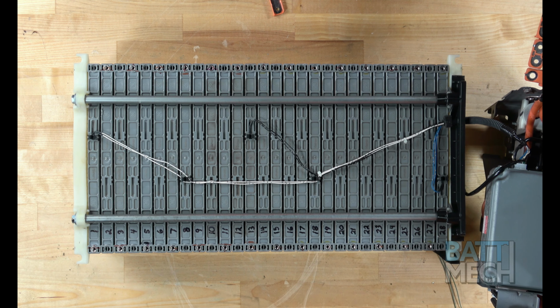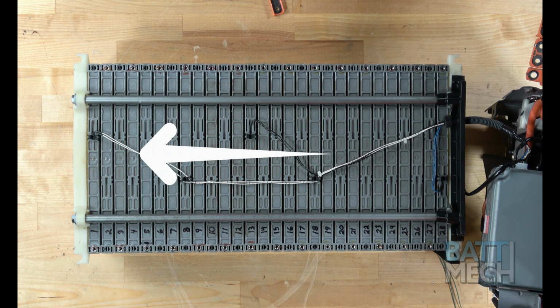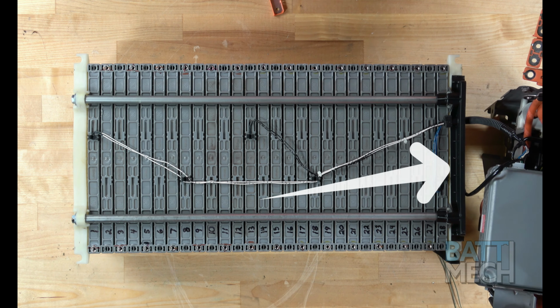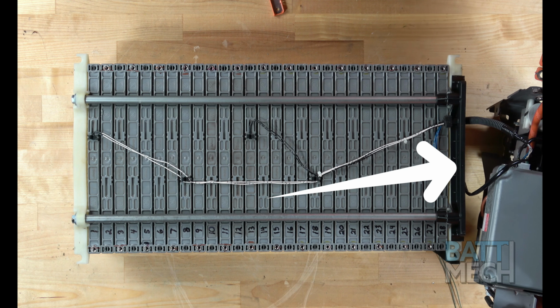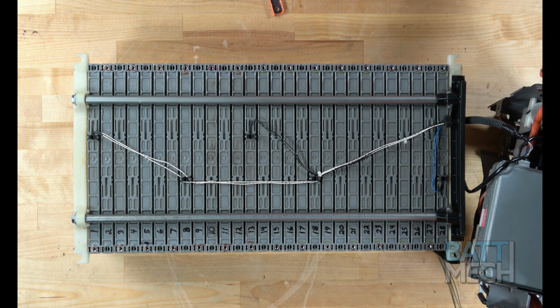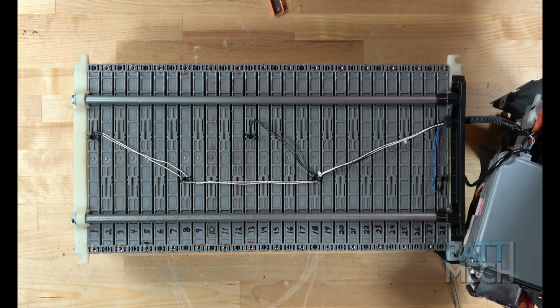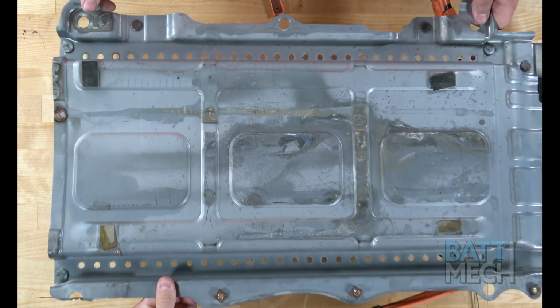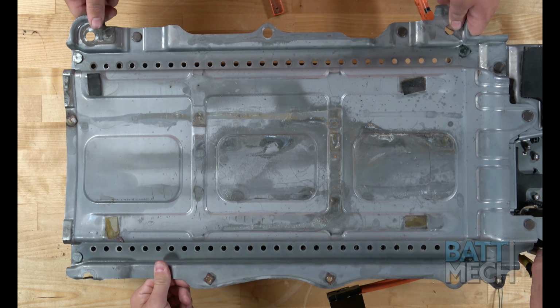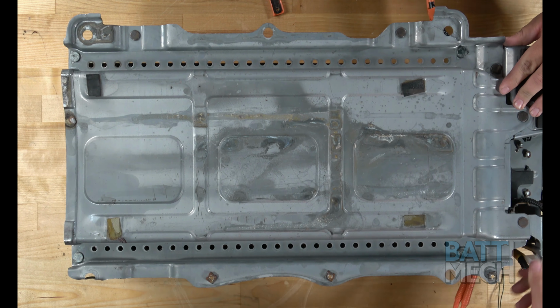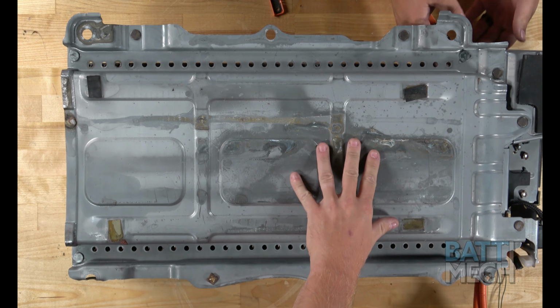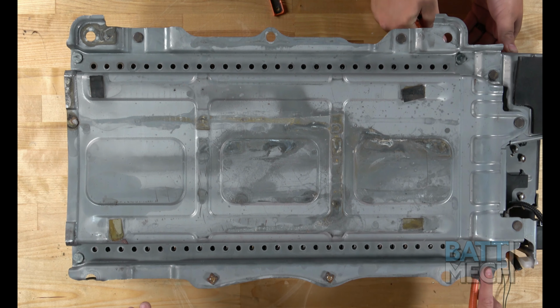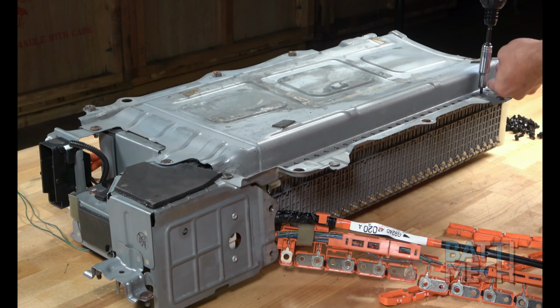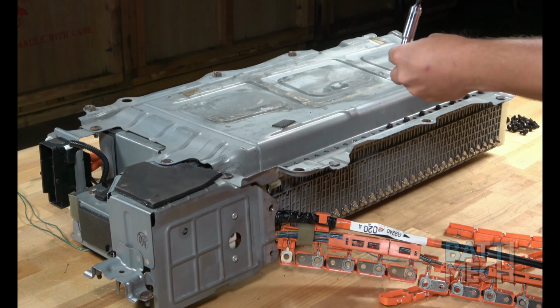Now you're ready to start reassembling the modules back into the case. Start by attaching the temperature sensor wires and replacing the black plastic cover on the bookend. Note, the number 1 module is to your left, the number 28 module to your right. Now that the sensor wires are in place, you can replace the bottom cover of the battery case. Use the new screws given to you by BattMech.